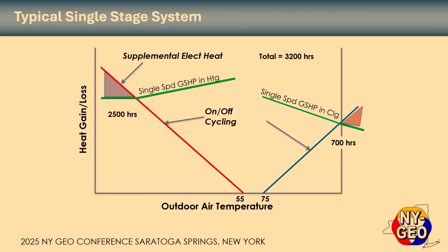On the cooling side, it works pretty much the same way, but you don't have any supplemental cooling typically, so you try and make sure that you've got enough cooling, and typically people will actually like to have a high runtime anyway for dehumidification, so they don't worry about this quite as much, but you do size mostly for cooling for traditional air source heat pumps. GEO, we've traditionally tried to size around the heating side.